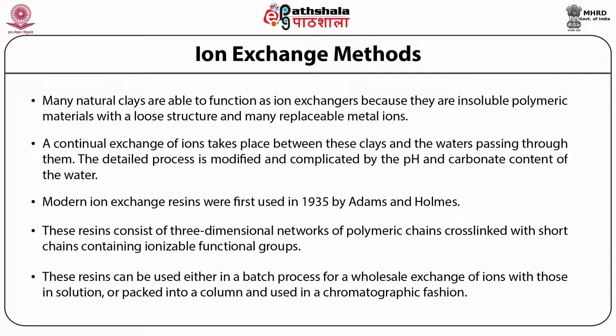Many natural clays are able to function as ion exchangers because they are insoluble polymeric materials with a loose structure and many replaceable metal ions. A continual exchange of ions takes place between these clays and the water passing through them. The detailed process is modified and complicated by the pH and carbonate content. Clays have varied and unreproducible properties, and it was only with the introduction of synthetic ion exchangers that a reproducible scientific technique became possible.